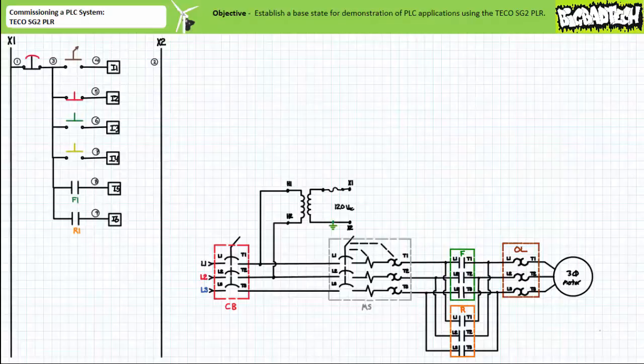Given this safe starting condition, our intention is to configure the TECO SG2 PLR in the following fashion. The PLC will make use of 6 field input devices: a normally open maintain contact selector switch on input 1, a normally closed momentary contact red push button on input 2, a normally open momentary contact green push button on input 3, a normally open momentary contact yellow push button on input 4, the normally open auxiliary F1 contact of the F contactor on input 5, and the normally open auxiliary R1 contact of the R contactor on input 6.